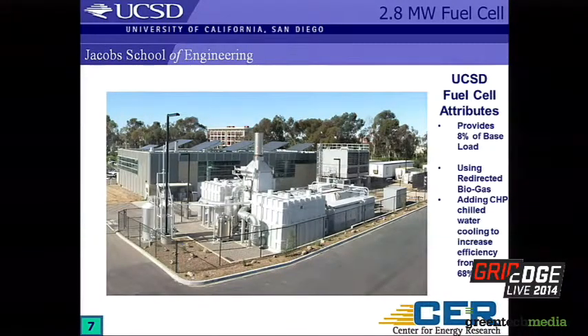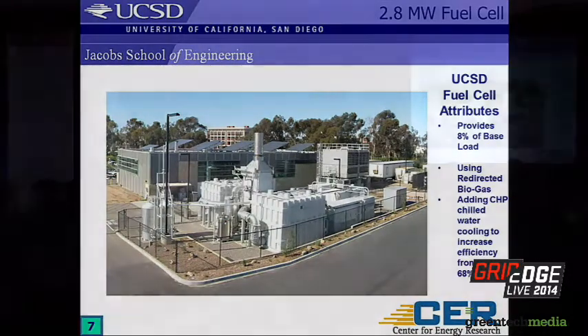The fuel cell is, like I mentioned, 2.8 megawatts in size. It uses redirected biogas. We actually worked a deal with the city of San Diego to capture the excess methane gas that they were flaring off to the atmosphere. So we capture that methane gas, reform it, and ship it up to UCSD via pipeline, where it's utilized at the fuel cell. That fuel cell runs 24/7 and provides about 8% of our base load on our system. So it's very efficient — about 42% efficiency.